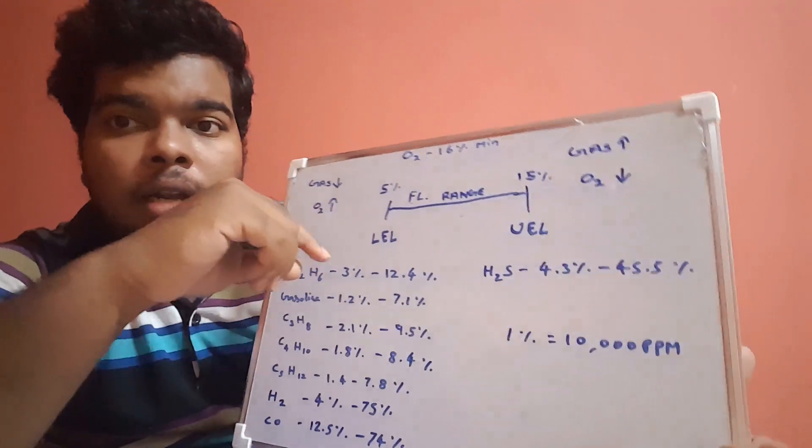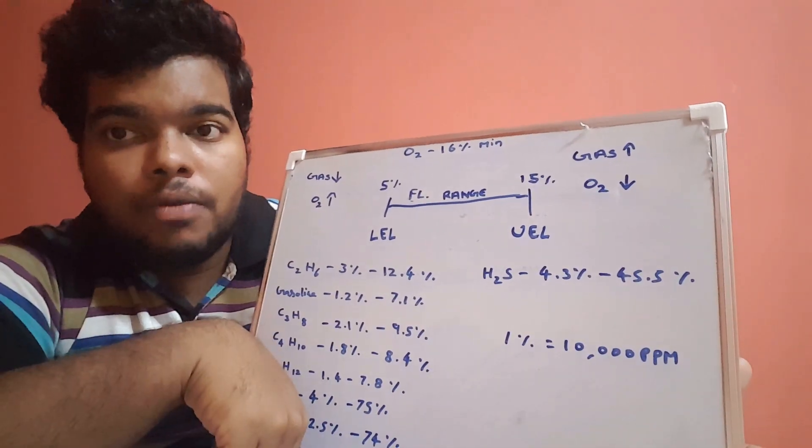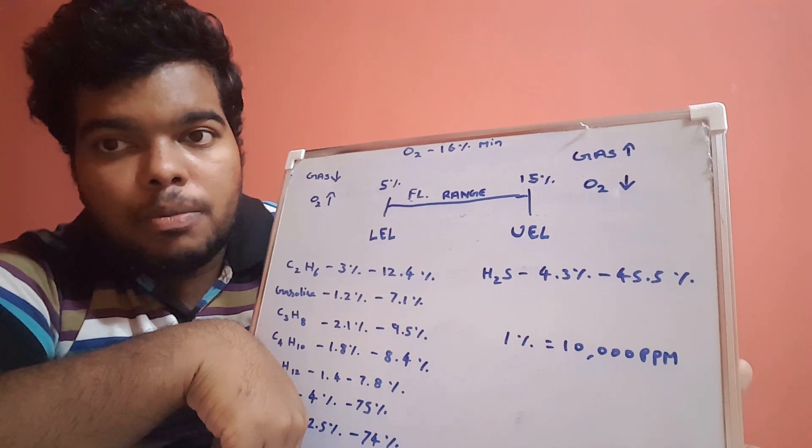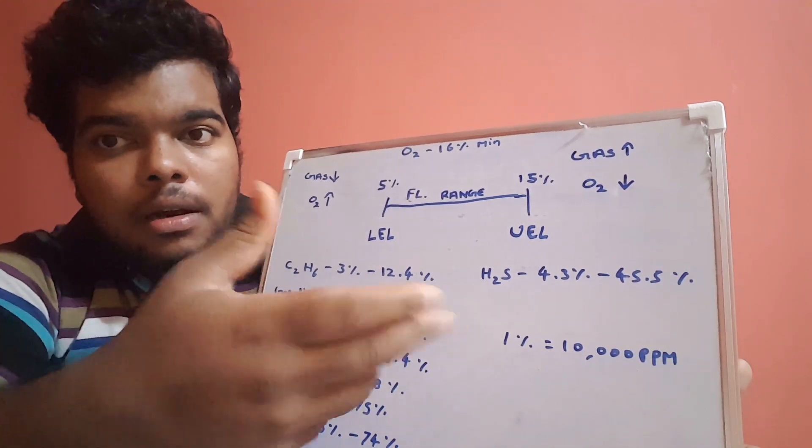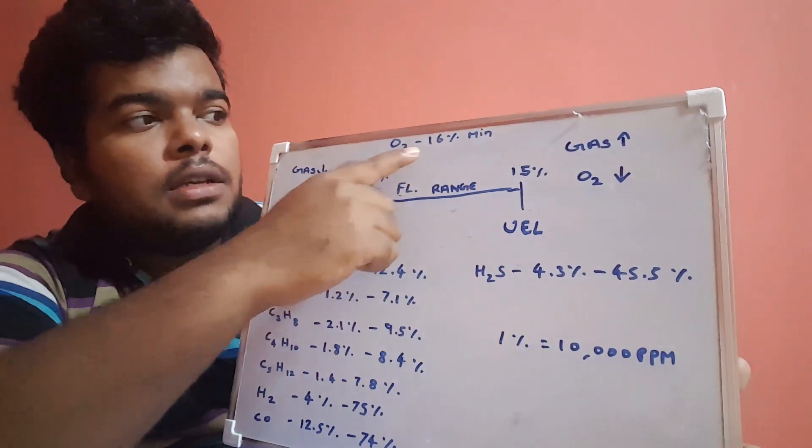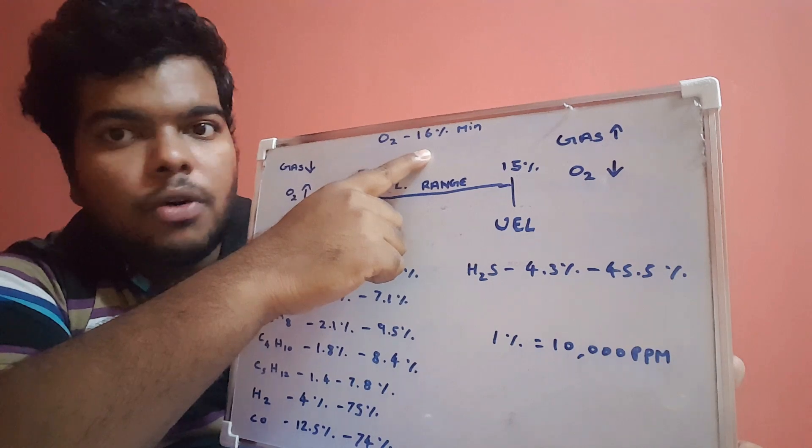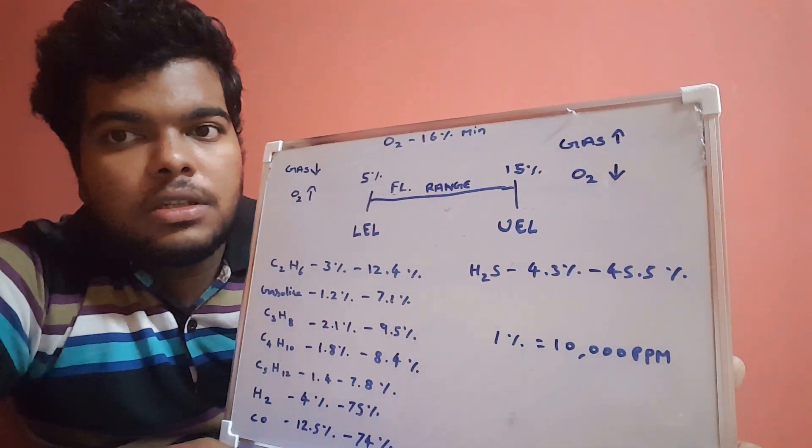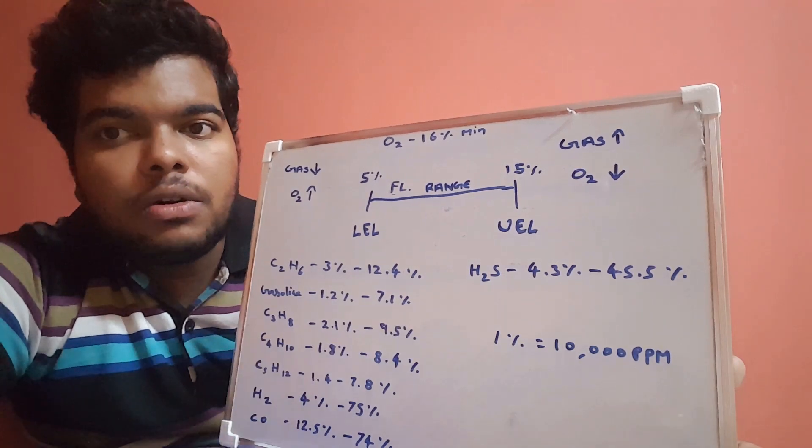Below 19.5 and above 23.5, it will give the alarm indication. For burning, we need at least 16 percentage of oxygen for normal combustion. Below 16 percentage, the ignition will not sustain and the fire will go off.